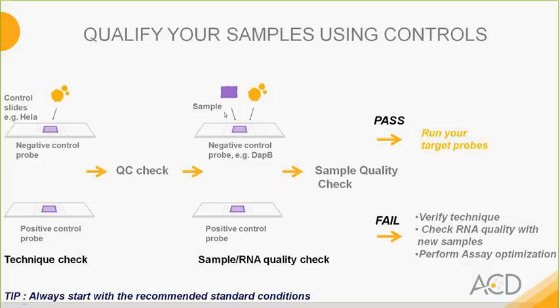You would hybridize the negative and the positive control probe on the samples and perform 2 things. What you're doing at this moment is checking the RNA integrity of your sample, based on the number of dots, the intensity, and so on. The other thing is you're looking for background, making sure that your negative control probe is yielding clean background. You're also assessing the pretreatment efficiency. So at this point, what you'll be looking at is intact morphology. What we don't want is over-digestion of the sample. We also do not want under-penetration of our samples.